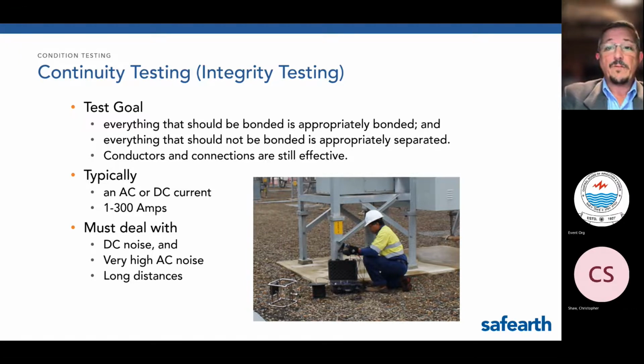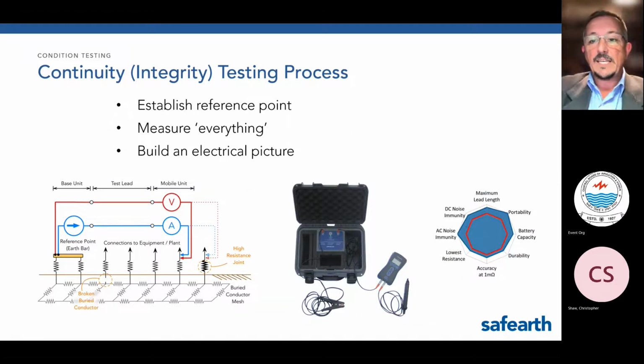Continuity or integrity testing is a powerful form of condition testing. It can identify not just broken or stolen connections or conductors, but it can even identify loose or deteriorated ones if the right equipment and the right approach is taken. Continuity testing can be carried out at every part of the substation and to every item in the station. This provides much greater accuracy than sample testing of specific points or a specific range of items only. It's testing every single thing. If the test instrument has good safety and noise immunity qualities, testing can be carried out in any station without de-energization or any disconnection.